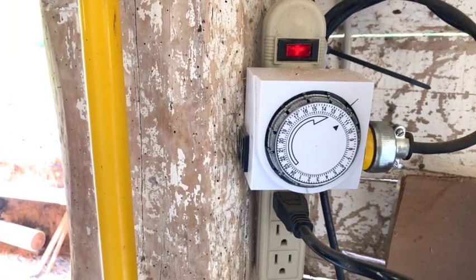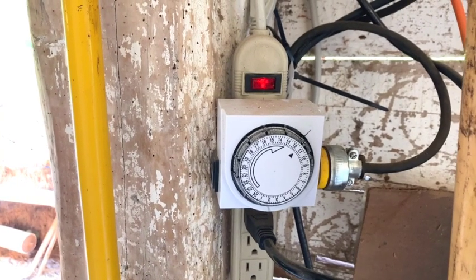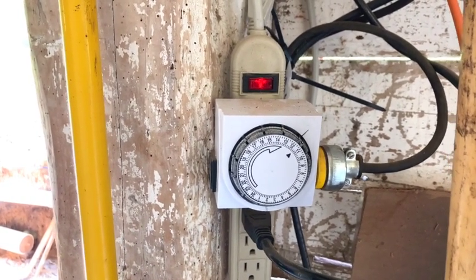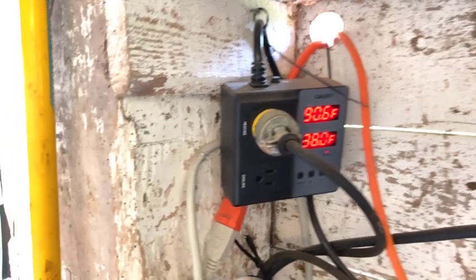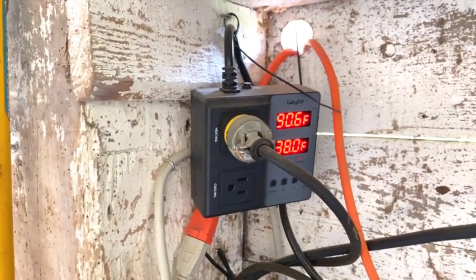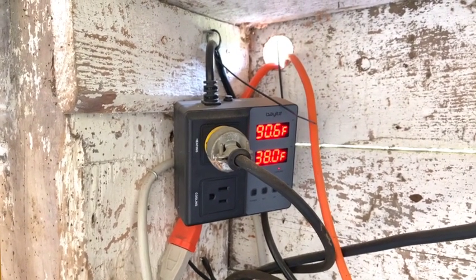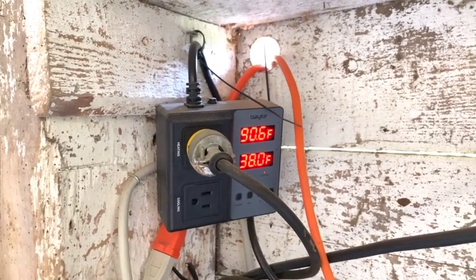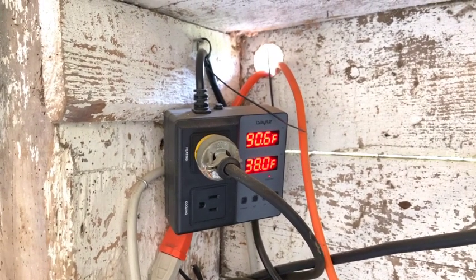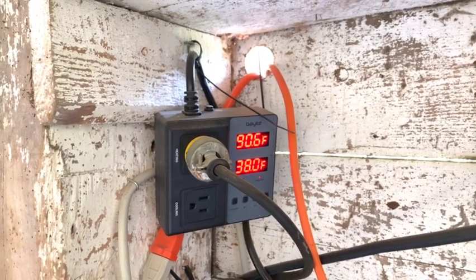I have this set to run on a timer, and that took a little bit of coordinating. I still don't know if I have it fully figured out because there are a lot of factors. Essentially, the thermostat will override whatever the timer is doing, so if for whatever reason the temperature drops below 38 degrees, the pump will kick on and warm up all the water and pipe until it gets back up to 38 degrees — just warm enough to not freeze up and cause damage.